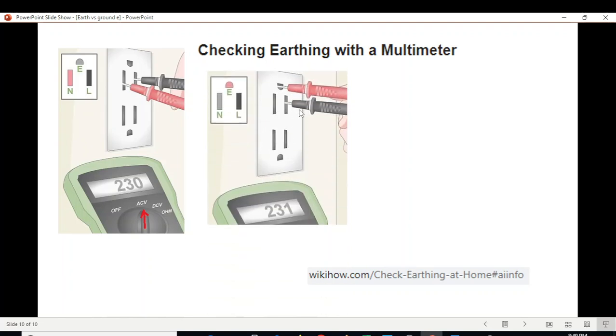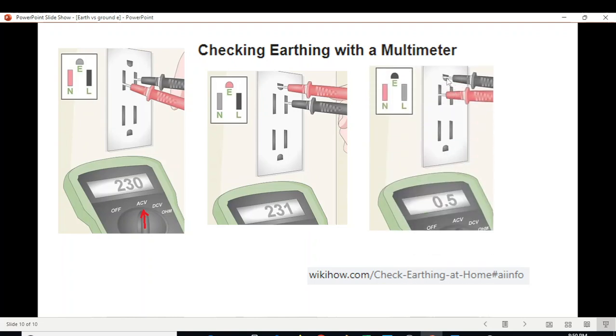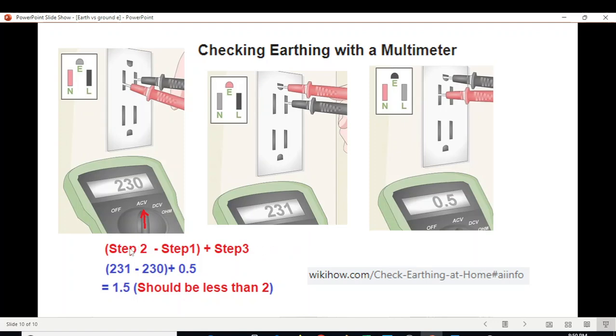The next step is that we connect the probe between earth and live. And let's say the voltage reading is now 231 volt. And the third step is that we connect the two probes between earth and neutral, and the voltage, let's say, is 0.5 volt. So the calculation that we should follow is step 2 minus step 1, that is 231 minus 230, plus step 3, which is 0.5, and it is 1.5 in this case. Ideally, it should be less than 2 volts if your earthing system is functioning properly. So I hope this gives you an idea about the whole scenario.